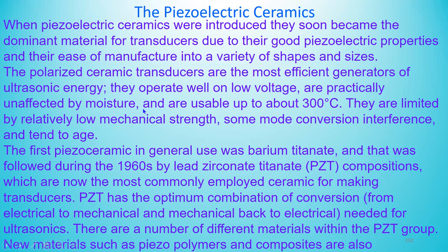When piezoelectric ceramics were introduced, they soon became the dominant material for transducers due to their good piezoelectric properties and their ease of manufacture into a variety of shapes and sizes. The piezo-polarized ceramic transducers are the most efficient generators of ultrasonic energy. They operate well at low voltage, are practically unaffected by moisture, and are usable up to 300 degrees centigrade. They are limited by relatively low mechanical strength, some mode conversion interference, and tend to age.